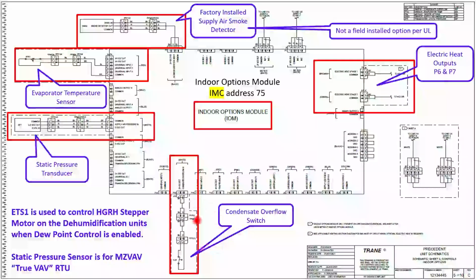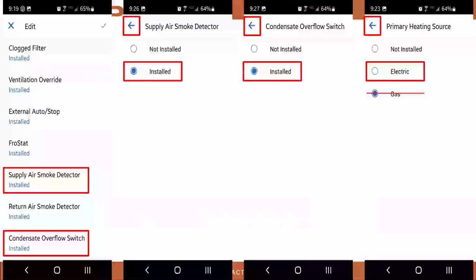Again, if you have one of these installed, but you don't have an indoor options module, it'll prompt you and tell you your communications are off. Again, here's how to edit it. Smoke, supply air smoke, installed or not installed, condensate overflow switch. You're going to just go right down the line.